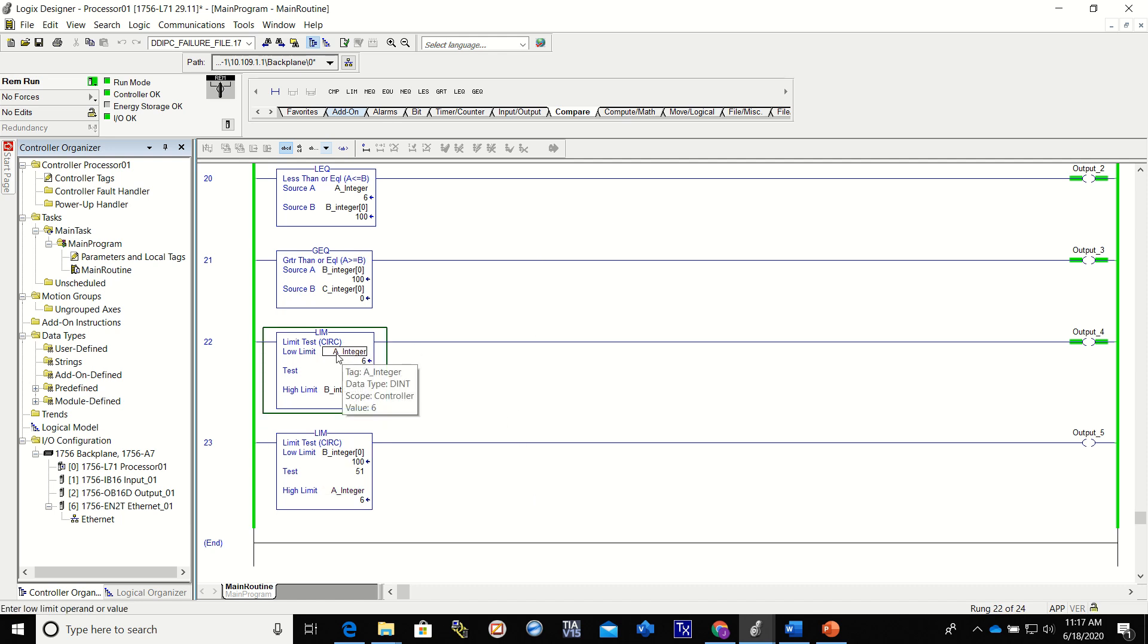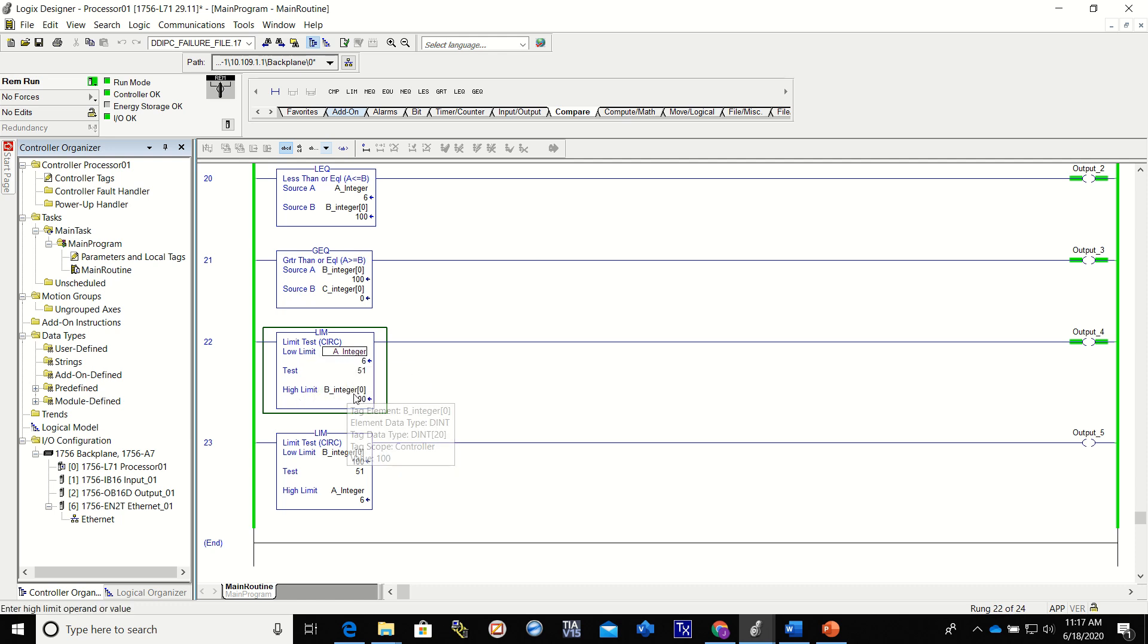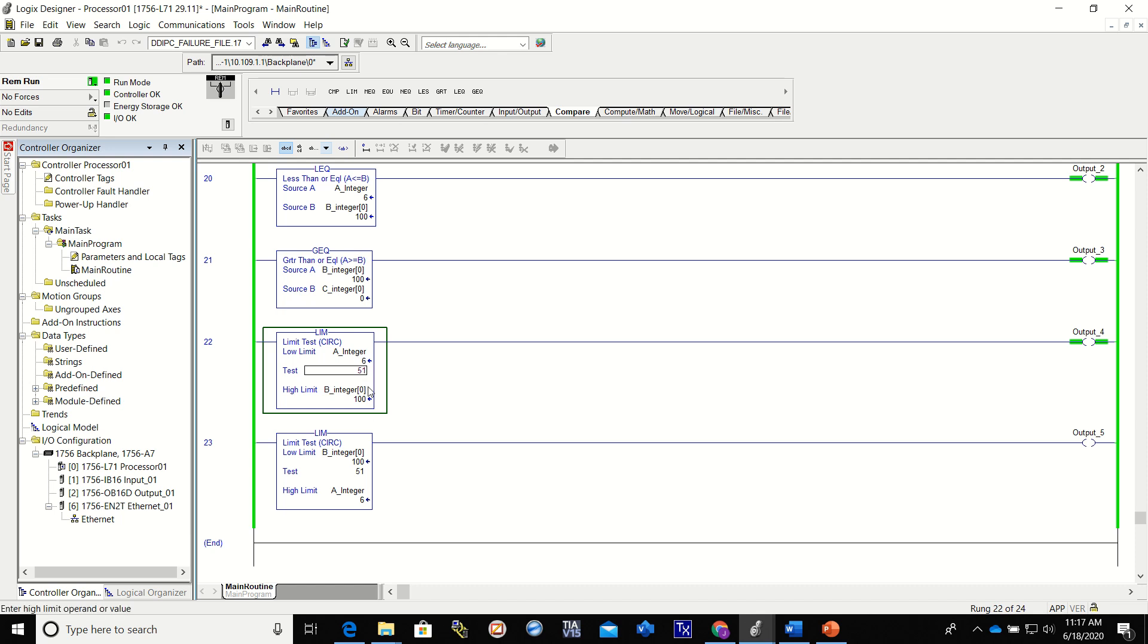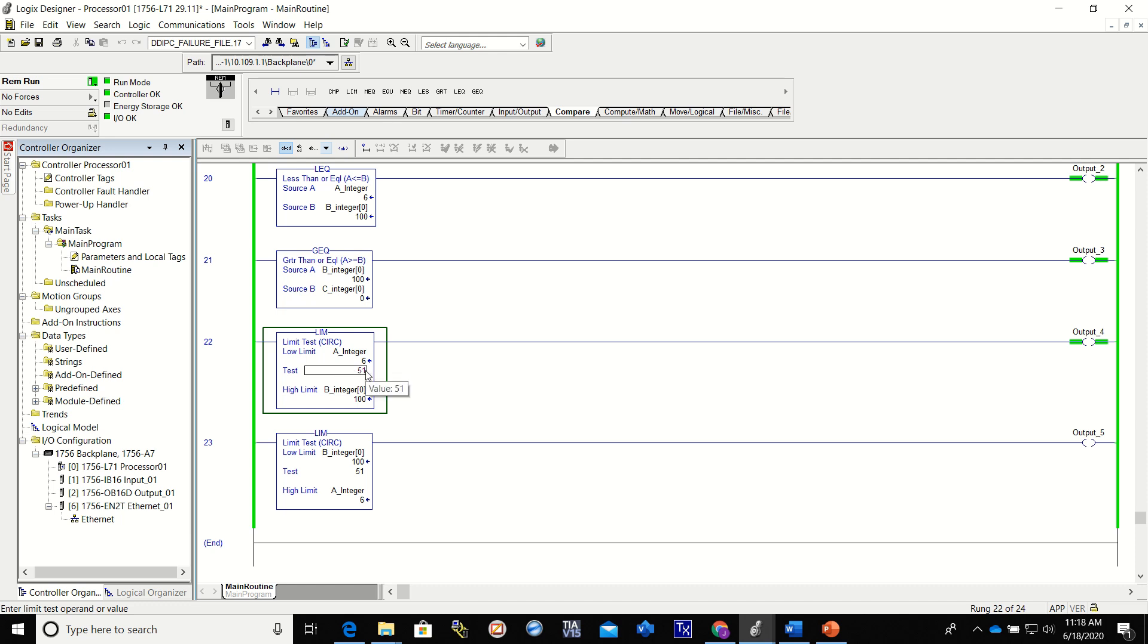I've got two of them on here, one here and one right here. So let's look at it. This one, the low limit is the A integer and the high limit is the B integer. What a limit does is it does a test for these two values. The low limit on this one is the value 6, the high limit is 100, it's testing for the value of 51.